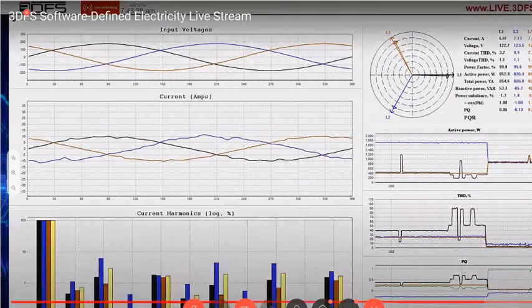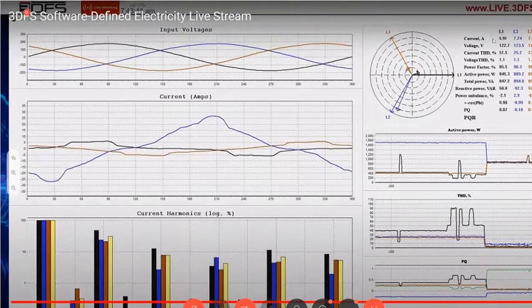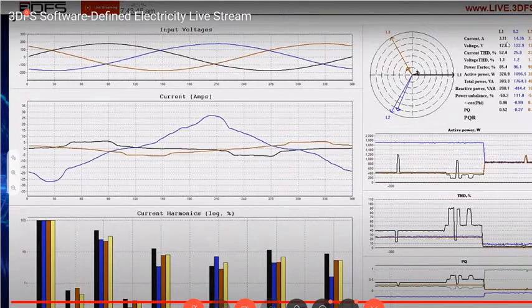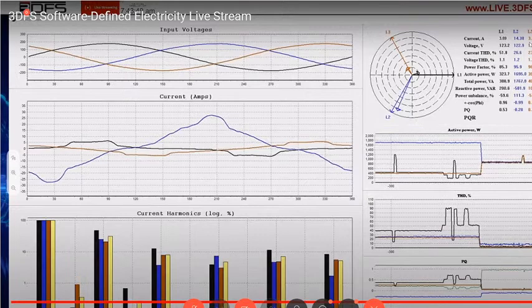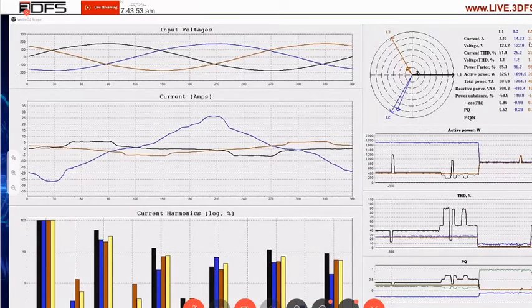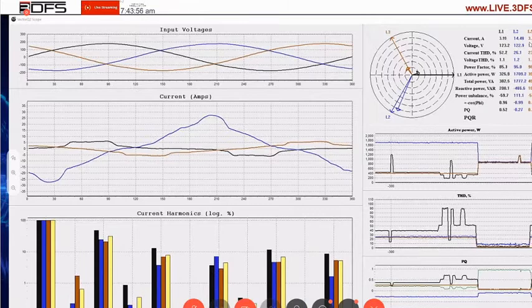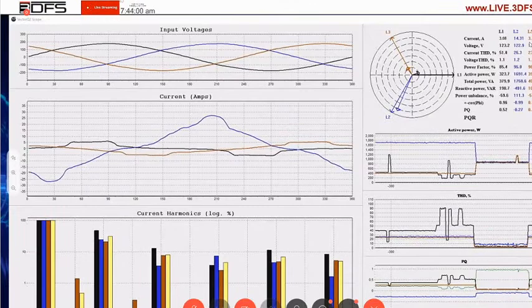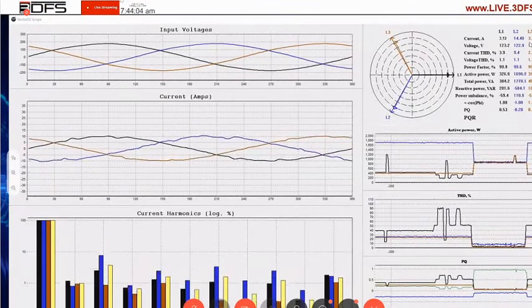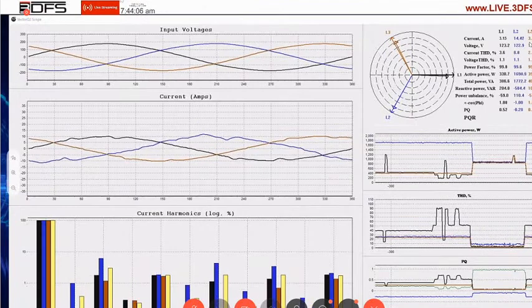Some things I'll point out right now: if you look on phase 1, it's 3 amps, phase 2 is 14 amps, and phase 3 is 3 amps. It's a small amount of power in this facility just because it's so early in the morning. But when I turn the device on, what you'll see is it immediately averages out to 6-7 amps per phase.